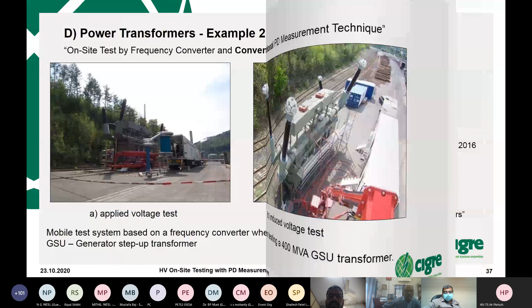This was nearly the end of my presentation. The technical brochure, as I mentioned, has 128 references, and the intention was just to say that high voltage test alone is not very successful, but you can combine it very well with partial discharge, even if the voltage stress or amplitude is like the operation voltage. You have different chances to look at the PD activity, and this is mentioned in it.